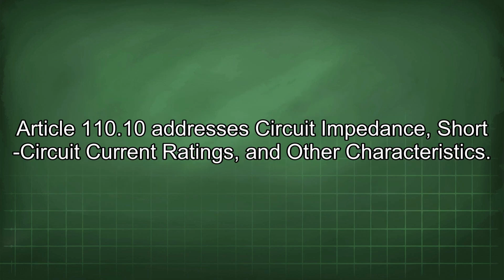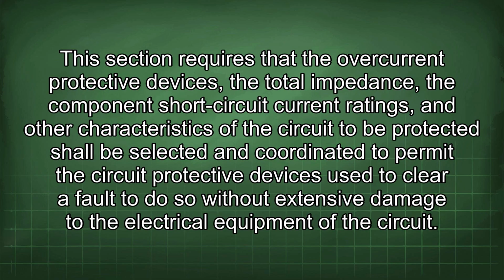Article 110.10 addresses circuit impedance, short circuit current ratings, and other characteristics. This section requires that the overcurrent protective devices, the total impedance, the component short circuit current ratings, and other characteristics of the circuit to be protected shall be selected and coordinated to permit the circuit protective devices used to clear a fault to do so without extensive damage to the electrical equipment of the circuit.